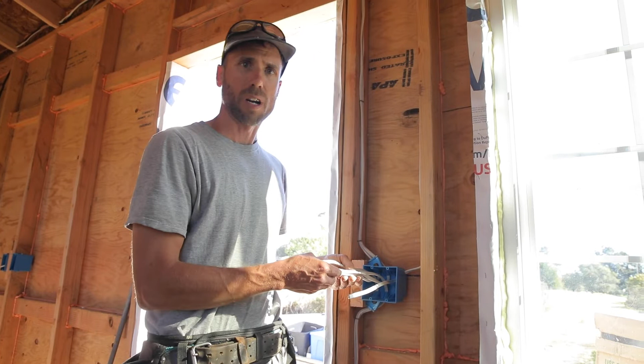Each box has numbers in it like you see here, telling you how many of each wire you can fit in. These are 14 gauge wires, and the number on the back of the box is 16-14, so we can fit 16 of these. But these are not wires, they're cables, because each is a bundle of wires — each has 2 wires in it. The ground is not counted separately; you're allowed to take all the grounds and count them as one. So this has 2 wires, 4, 6, 8, 10, plus all the grounds is 11.